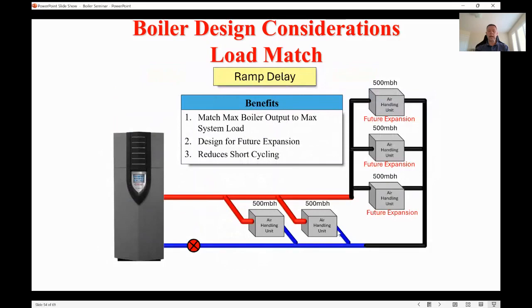Another cool thing that these guys have in here is sometimes you can control how aggressive not even just the boiler itself, but the boiler plant will operate when using the onboard controls. So let's say you have a situation like this. Maybe you have a building here that has future expansion. So what do we got? When the future expansion goes here, we have 2.5 million BTUs here. Well, we're buying this boiler today. So we put in a 2.5 million BTU per hour boiler, but 1.5 million isn't running.